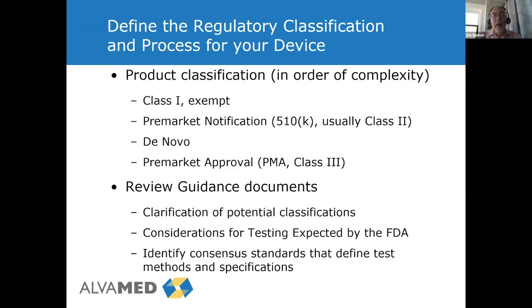So let's talk a little bit about regulatory classifications. There's class 1, 2, and 3. Class 1s are exempt - you still need to document your decision why they're exempt, and these can come out of the classification. There is a classification database where you can search the description of your product and get a product code and a classification from that. Second is pre-market notification, that's 510K. These are generally class 2s.